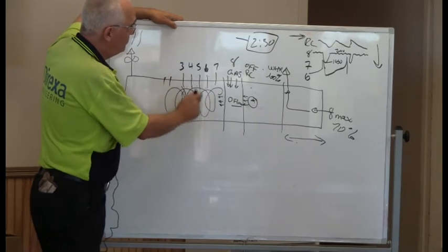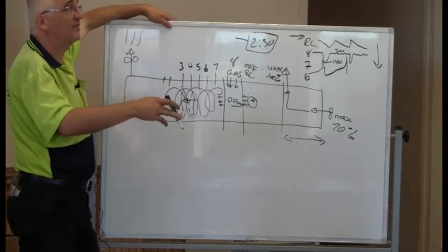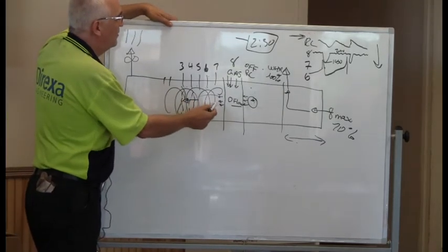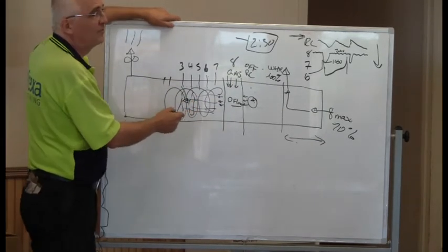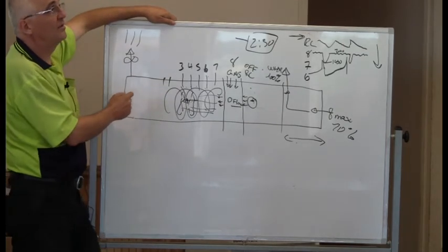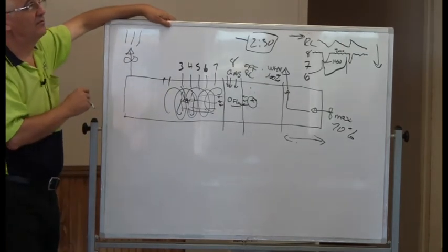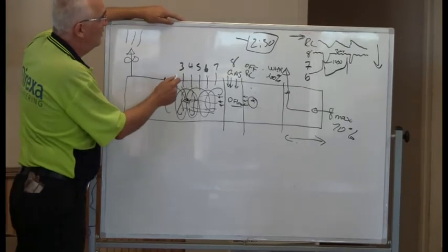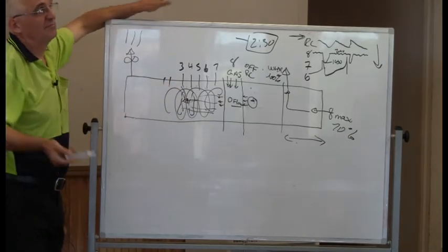This is just here to burn the gas, with constant air, because the input of gas is going to be consistent, and you want to burn it before it arrives in the preheat, because in the preheat it starts to be too cold for the gas to actually burn properly. So if you don't burn it in those stick lengths, it's a waste.